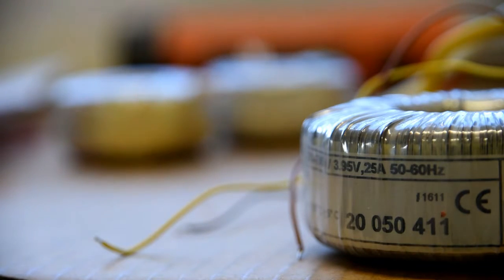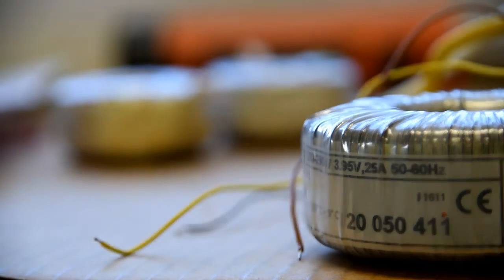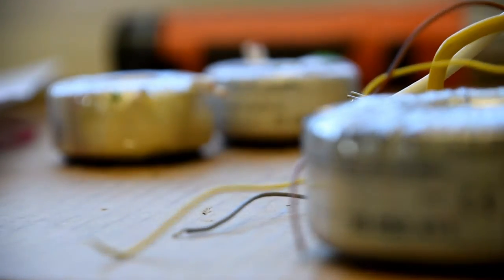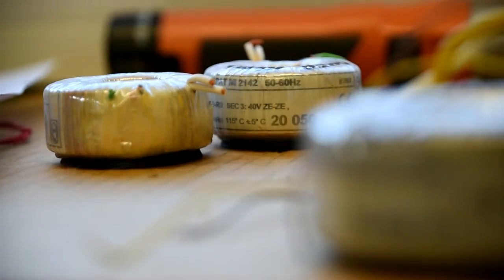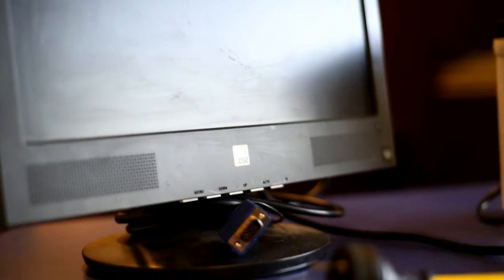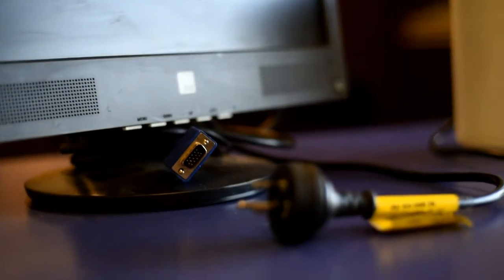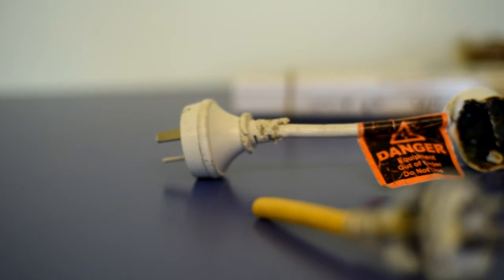Low current testers are incapable of testing at 10 or 25A, and they meet current compliance standards by only executing an earthcontinuity test. We think of it as an IT standard because it doesn't put sensitive electronic equipment at risk. This is a non-stress test that doesn't check the integrity of the protective earth.